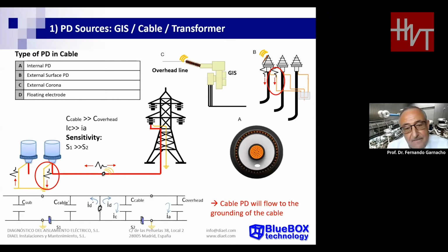In any case, we can measure the partial discharge through the cable sheath. The cable sheath, the screen of the cable, carries the partial discharge pulses, and in the connection of the cable sheath to the earth we have a good opportunity to measure partial discharge pulses using a special sensor: high frequency current transformers.